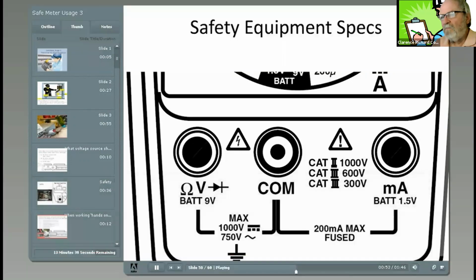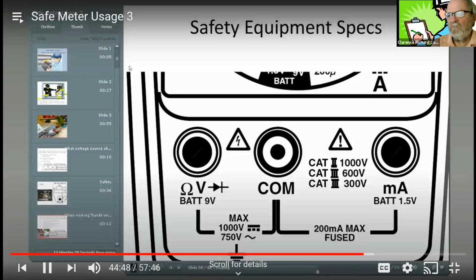That symbol can only be used if the product successfully completed testing to the agency's standard, which is based on national or international standards. UL 3111, for example, is based on IEC 1010.